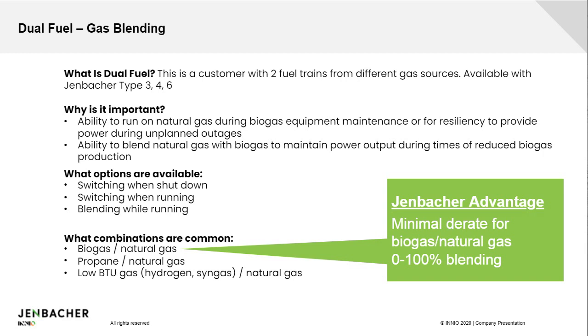So why would you want to do that? Well, for example, if you're running normally on sewage gas, but during a resiliency event, which might mean that the sewage gas is no longer available, or maybe there is any other plant outage which leads to an issue on the biogas supply or maintenance of the equipment, then you can switch to natural gas and then run the plant on natural gas to continue producing power. And that's potentially especially important if you have an outage of the electric grid at the same time, so you can island your sewage treatment plant and continue operating all the pumps and keep the sewage and the water moving. So that's one important aspect.